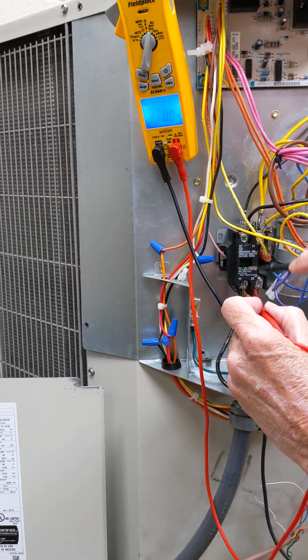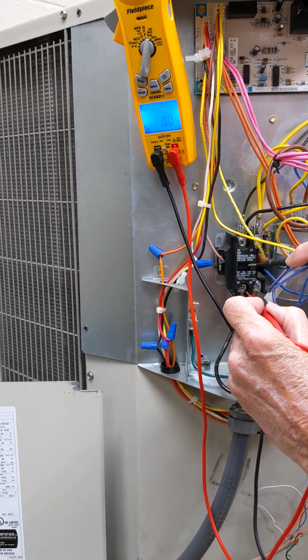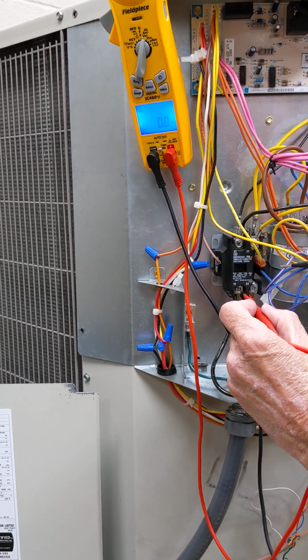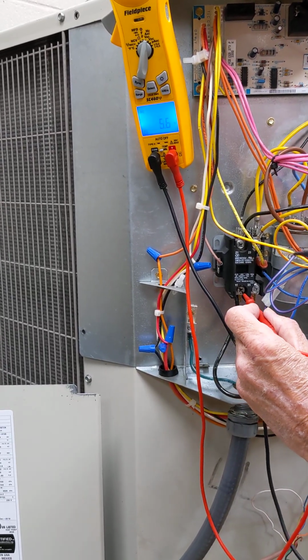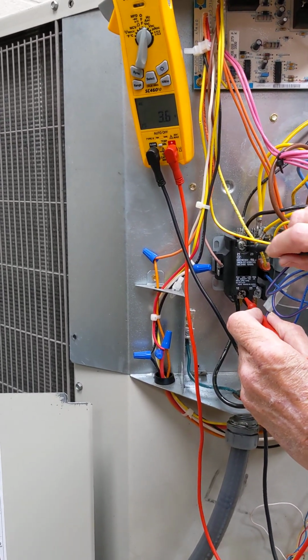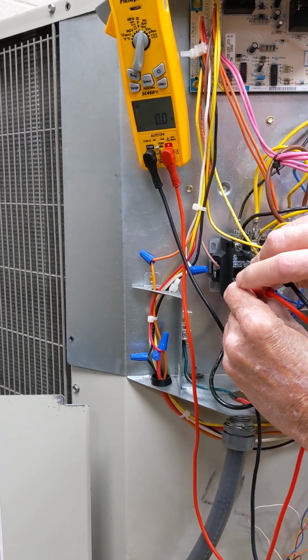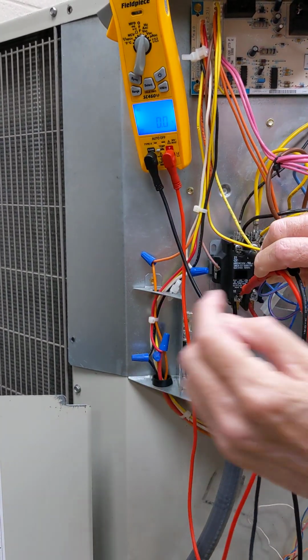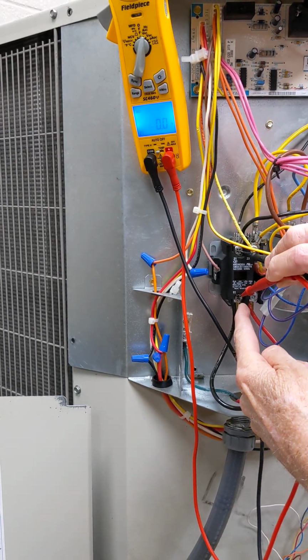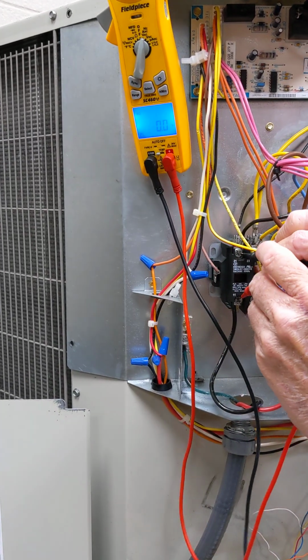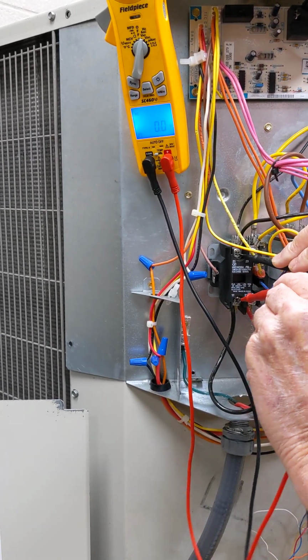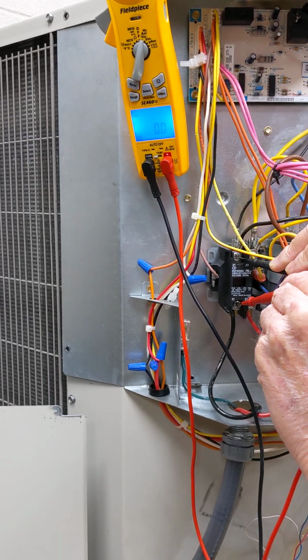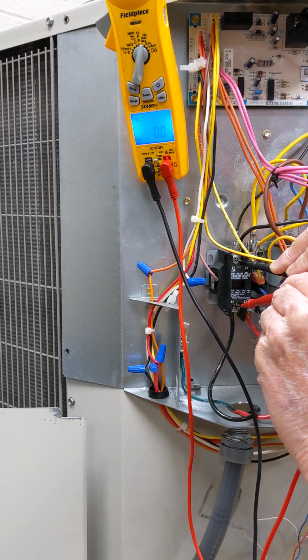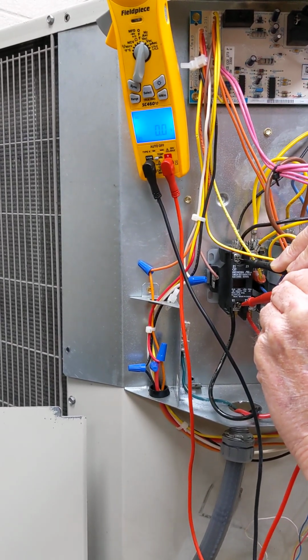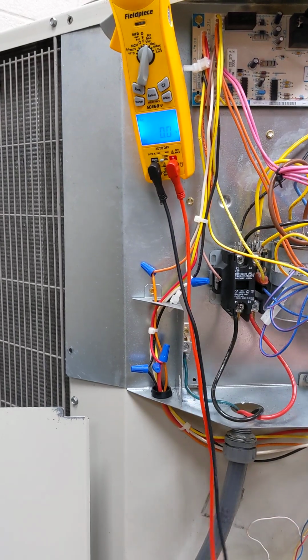Now the switched leg, this is the leg that has the switch in this case. If I measure across the switched leg, I have zero. That means it's letting all the power coming in get out. If I had a power loss or drop of 3 volts or more, that's an automatic replace the contactor.